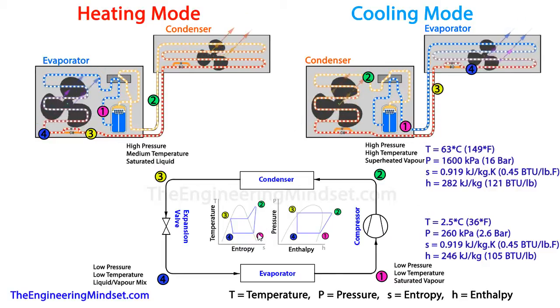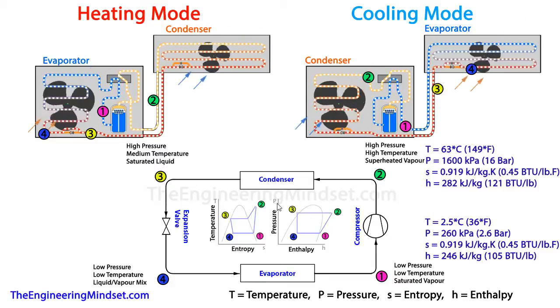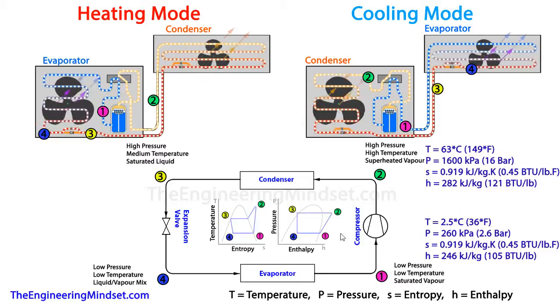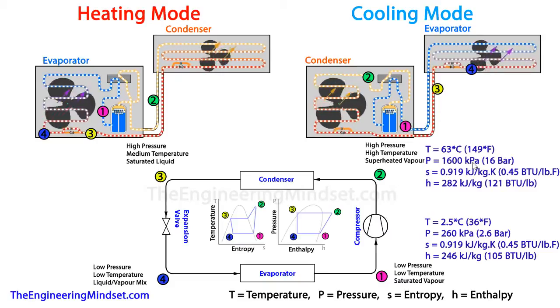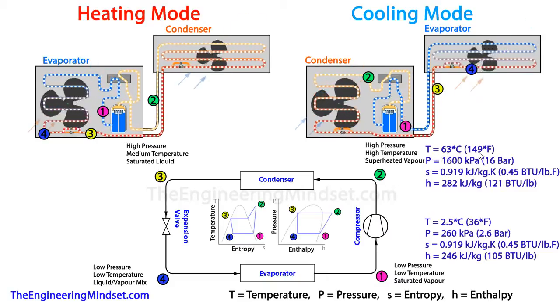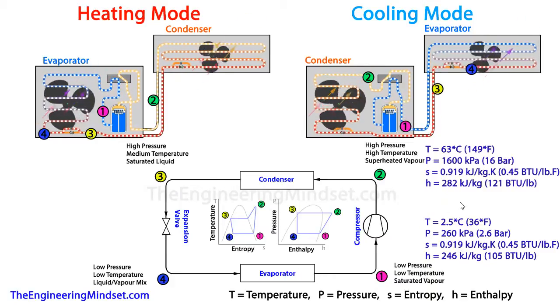At Point 2, after the compressor, we can see from the charts that temperature, pressure, and enthalpy all increase. The pressure has raised to 1600 kPa (16 bar), resulting in a temperature of 63°C (149°F). The entropy remains roughly the same, but enthalpy has increased to 282 kJ/kg (121 BTU/lb).